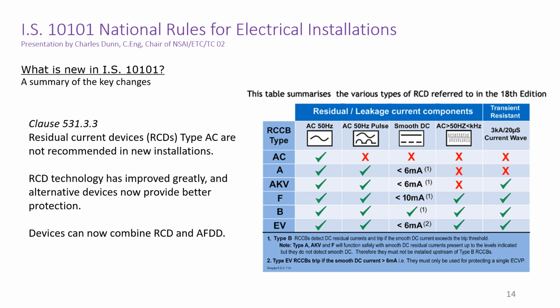Another huge advance in RCD technology is that some manufacturers can now incorporate both RCD and also arc fault detection, AFDD, technology in the same device. Manufacturers and suppliers are responding to the new possibilities that electronics brings to provide devices that improve the safety of the electrical installation. Look out for suppliers' presentations and demonstrations, many of which are on the web.